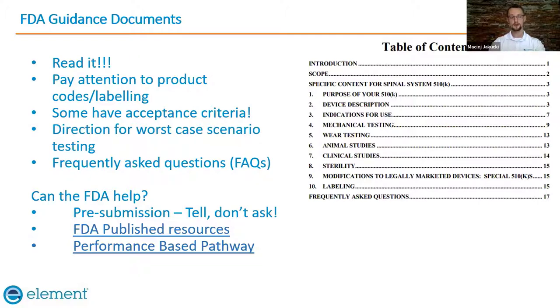We talked a little bit about the differences between the ranges of devices, and in a worst case scenario you might have to do a couple of different things. You want to identify which of your devices is most likely to fail, and provide either digital simulation data or feasibility testing if you're not sure, because you're going to have to explain to the FDA why you picked that particular size.